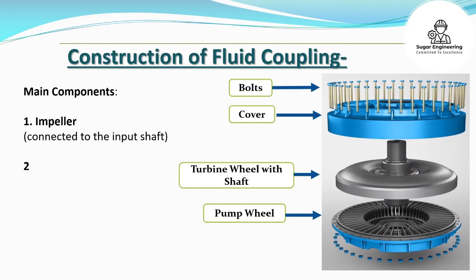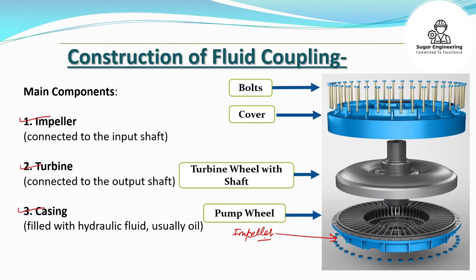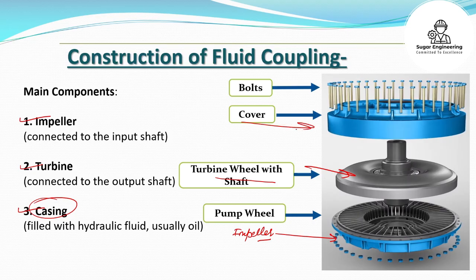Here we will discuss the main components of the fluid coupling. Generally, there are three main components. The first one is the impeller, the second is the turbine, and the third is the casing. This is the impeller, also known as the pump wheel, and it is connected to the input — it can be connected to a motor. The second one is the turbine wheel, which is connected to the output shaft and contains the turbine blades. The third one is the casing, which is filled with hydraulic fluid — generally we use oil. The bolts are used for the assembly of all three components.